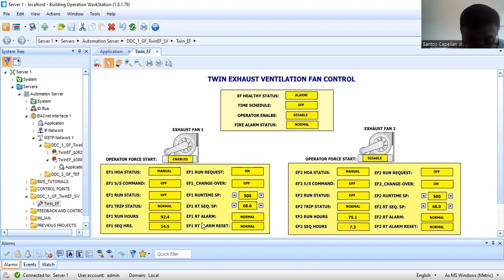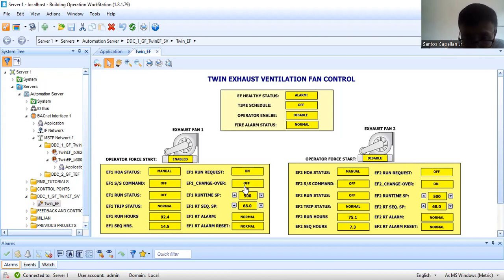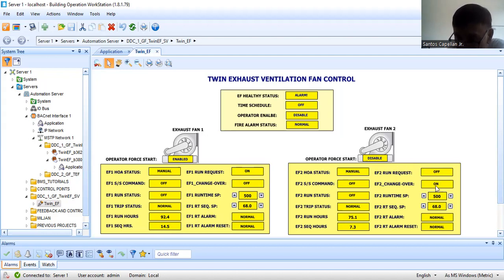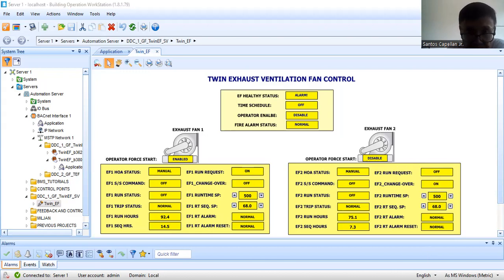In my program, what I have done is: if the sequencing time is above the set point, then it will be reset back to zero or a small value. Then EF1 run request will be on, EF2 run request will be on, and EF2 changeover will be on. That is how the program works. Let me show you my script program.